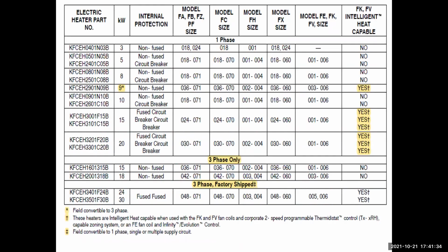Here are some of the selection options for the heaters that we have. So we look over here and we see we got a 9 kW heater with an asterisk. And this one's letting us know that, hey, this one is field convertible to 3-phase. And we come over here and we'll talk about intelligent heat later on. And they're letting you know that these are the approved ones that will be able to give you intelligent heat. So if you're looking for that, you'll be targeting these. Here's some units to make sure that these are 3-phase only. So if you're in a single phase, you would stay away from them.